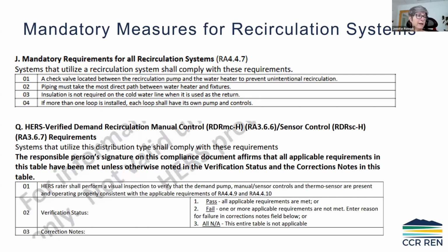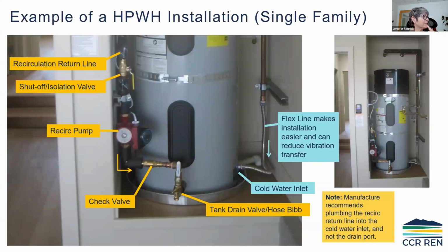Then there's another piece, if you're looking at multifamily specifically. Multifamily code says you need all your pipes insulated, but also there's an installation issue, let me look over for the slide. There is an installation on heat pump water heaters that we do not recommend, that we see in single family and that is explicitly disallowed under multifamily code. In Title 24 Energy Code, this is not allowed: that's where the return is actually plumbed into the tank cleanout at the bottom of the tank.